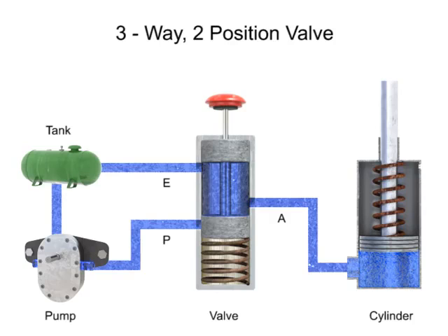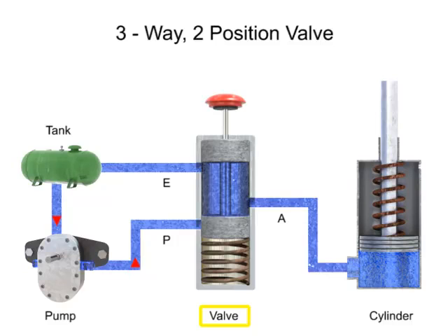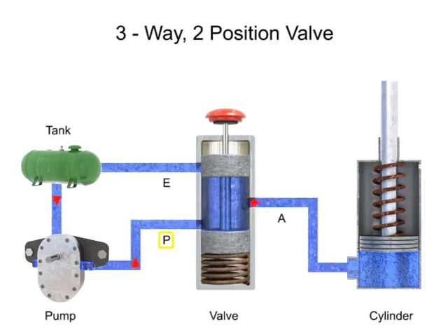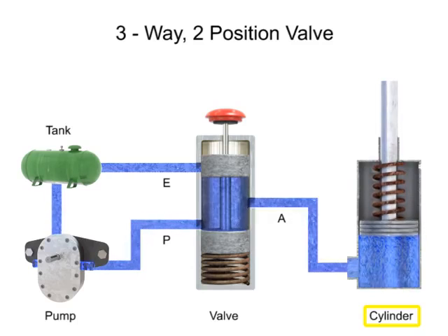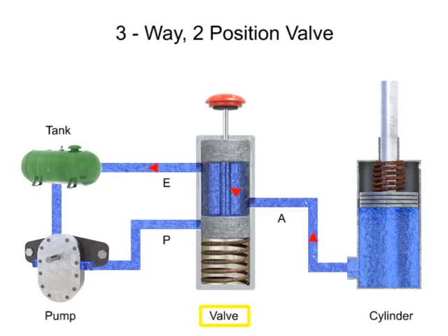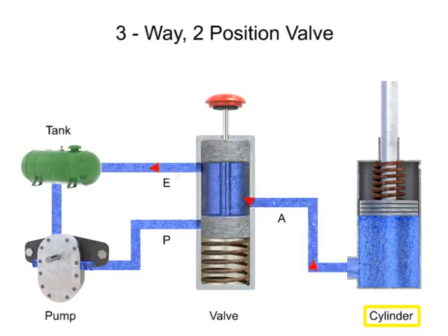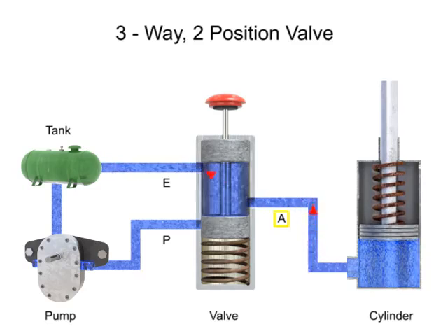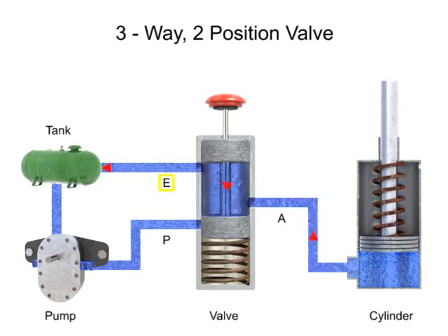Three-way directional control valves have many applications in fluid systems. One of the most common applications is for the control of single acting cylinders. In this application, fluid is pumped from a tank to pressure port P. With the valve in the normal position, fluid is blocked. When the valve is actuated, fluid flows from pressure port P through outlet port A to the cylinder. The cylinder extends and remains extended until the valve changes positions. When the valve de-energizes, the spool returns to position 1, pressure port P is blocked and exhaust port E is opened. The cylinder retracts and fluid flows from the cylinder through port A and out exhaust port E. From there, the fluid returns to the tank.